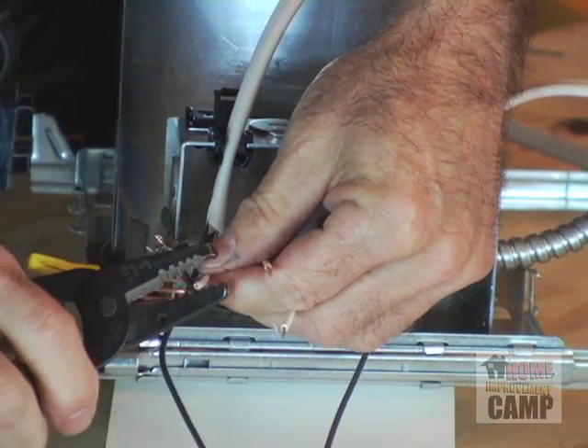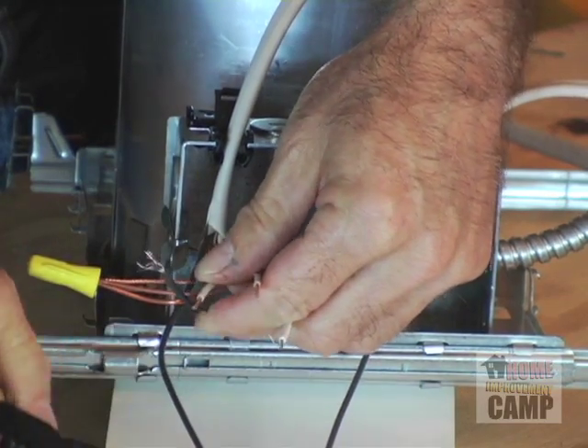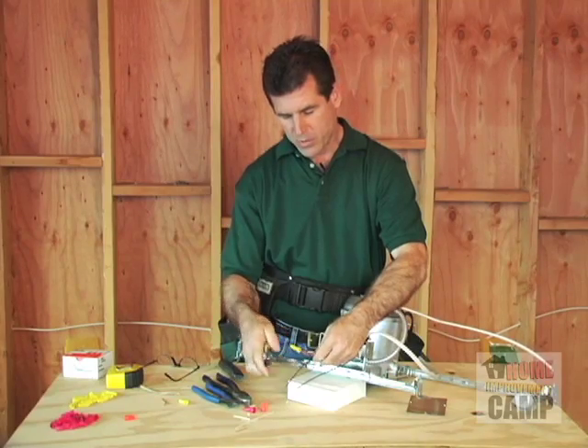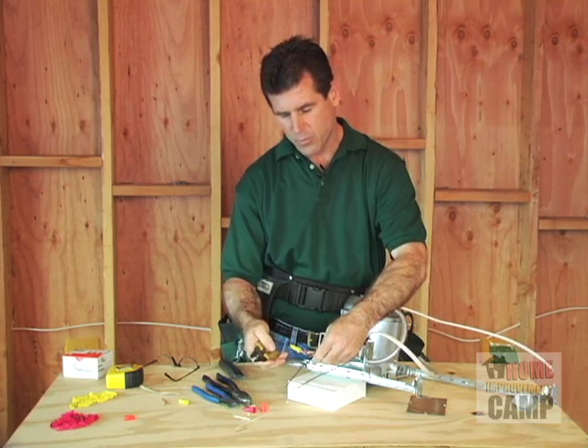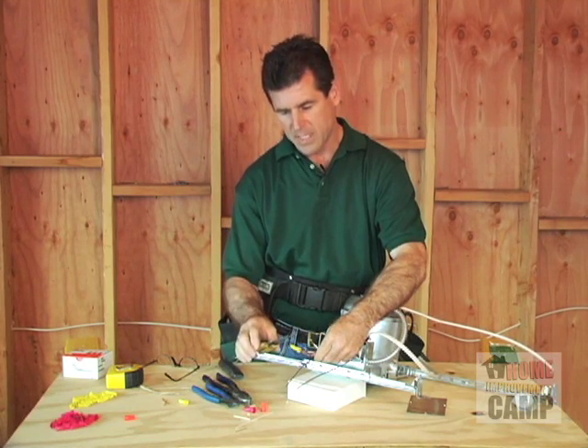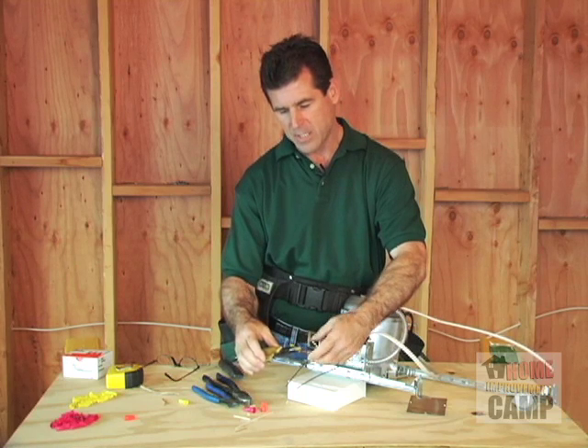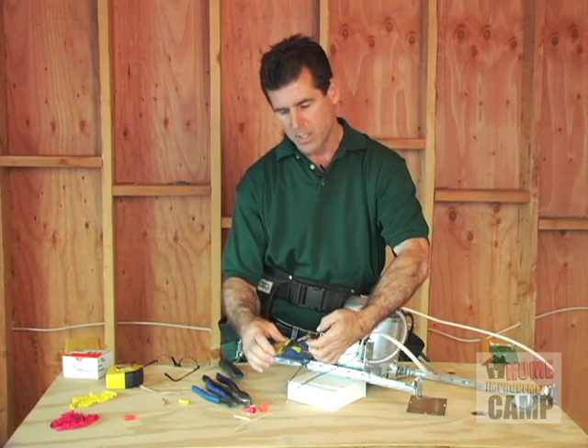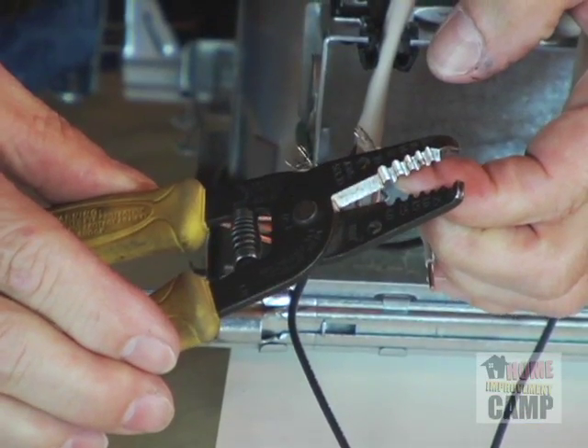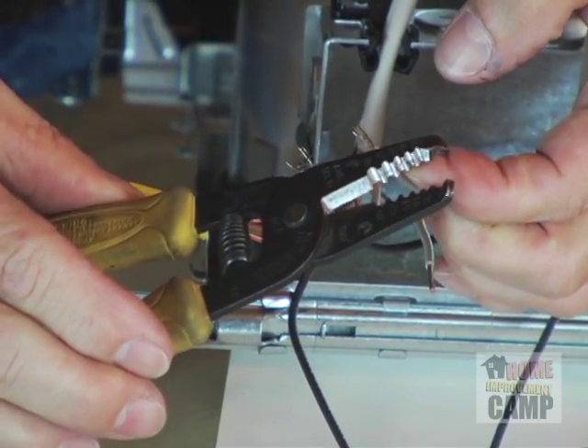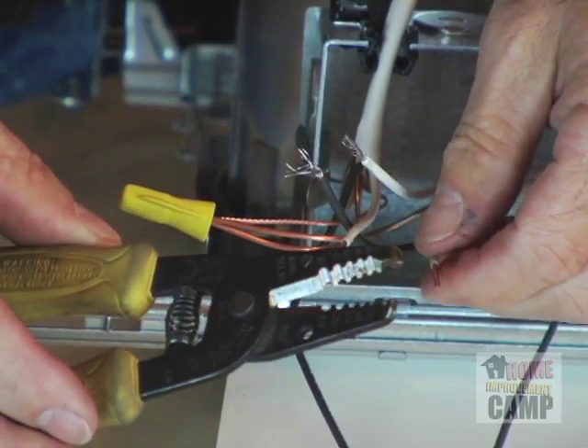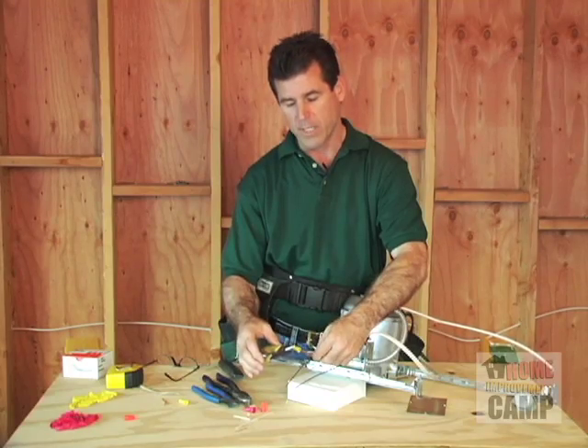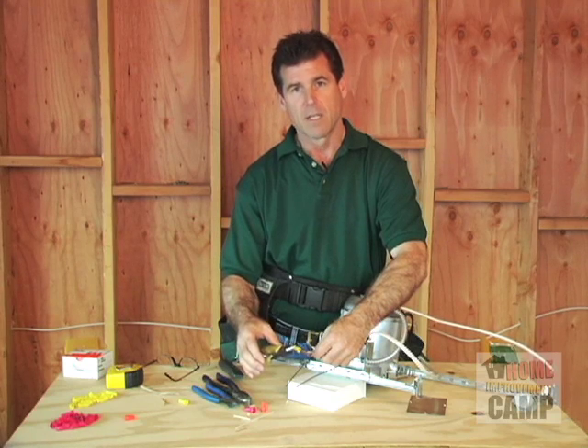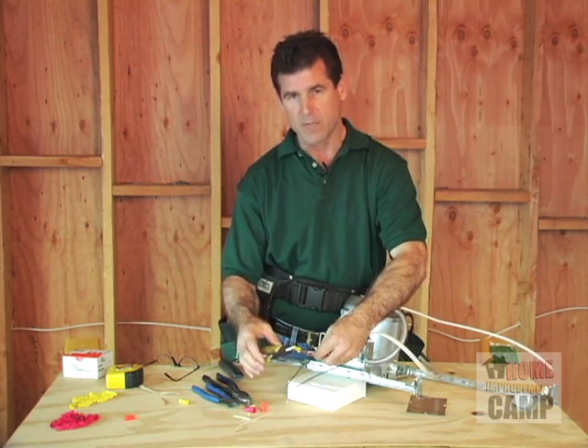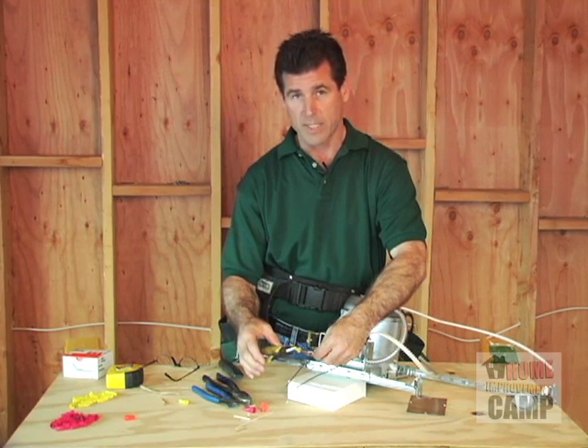Strip them off approximately 5/8 to 3/4 of an inch. I'm using a stripper with different size holes for different wire sizes: the largest hole is for 10 gauge, then 12, 14, 16, and 18. In this case, we're using 14 gauge wire, which is primarily used in a residence for lighting and convenience outlets. The smaller the number, the bigger the wire.